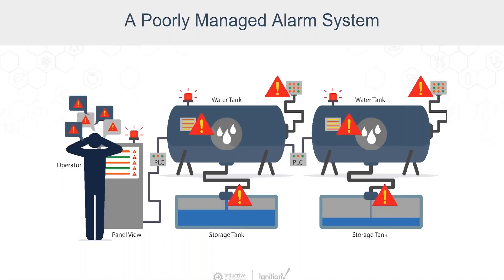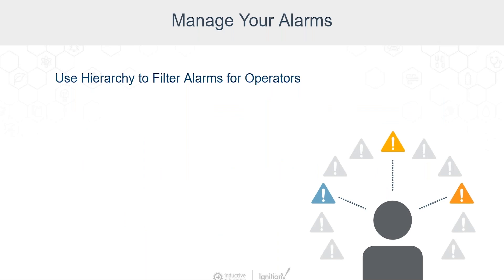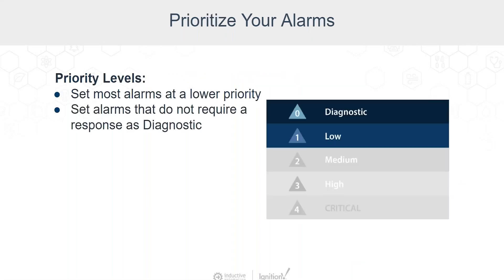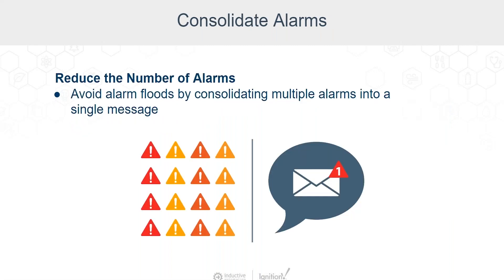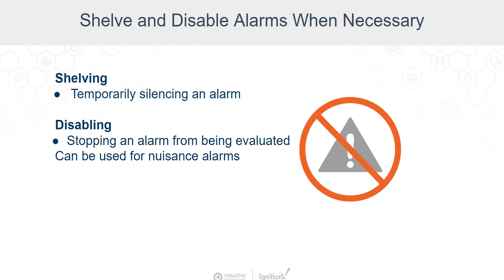A poorly managed alarm system creates problems for users. Alarm flooding means multiple alarms fire in a short period. Stale alarms stay in the alarm state continuously for hours on end. Chattering alarms go from active to clear multiple times per minute — users are going to silence these and stop paying attention. It's really important to manage alarms well. Filter them so you're only showing alarms to users in certain groups or when they've navigated to certain areas. Watch your priorities — create alarms with a low priority by default, and only the most important alarms should be high or critical priority. You can reduce your alarm count by consolidating messages into a single message, and you can shelve an alarm to temporarily silence it or disable alarms for equipment that is down for maintenance.